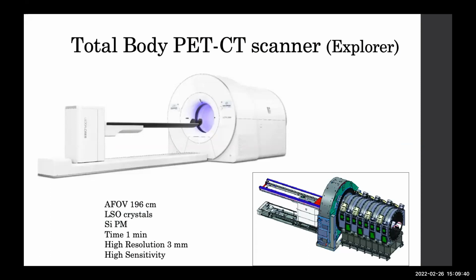Now the recent advance in PET CT scanners, for the last 1.5 to 2 years, is the total body PET CT scanner, which is named the uEXPLORER. This has a long field of view, so you complete the whole PET CT scan of the entire patient within 1 minute or less. It has LSO crystals, you can see here, the long axial field of view, and silicon photomultiplier tubes are used. The whole body, 165 to 170 centimeters of length of the patient, is covered in around 1 minute. It has high resolution, high sensitivity. The only problem is the cost.